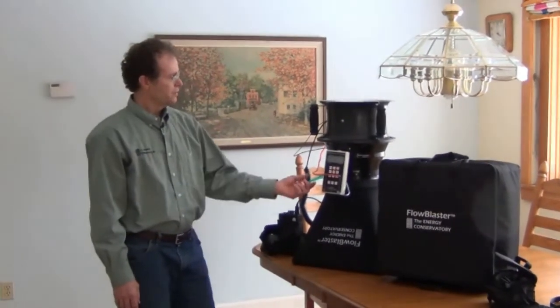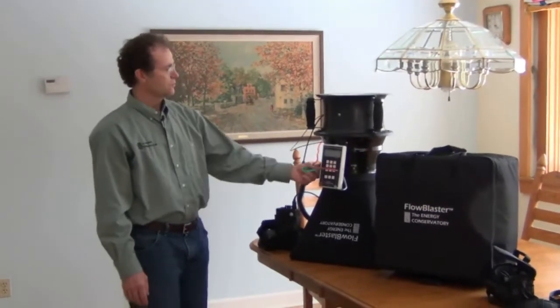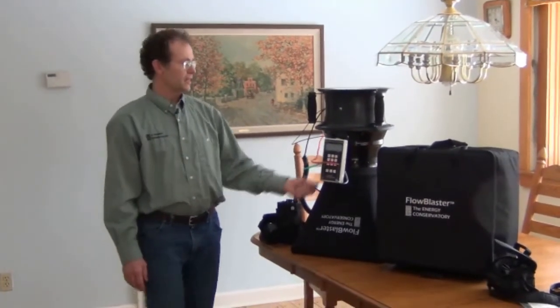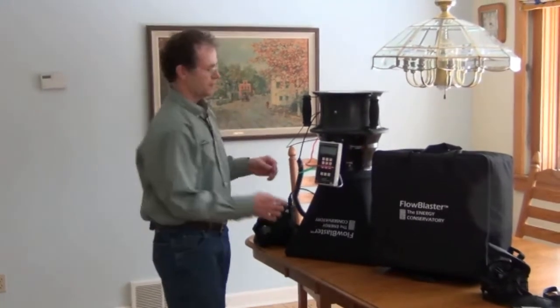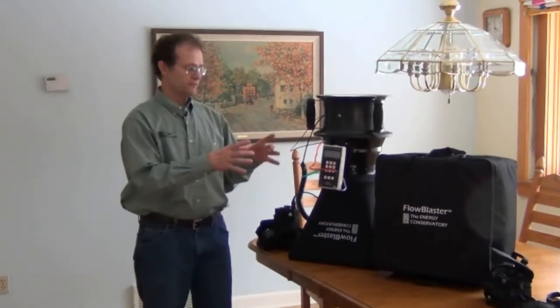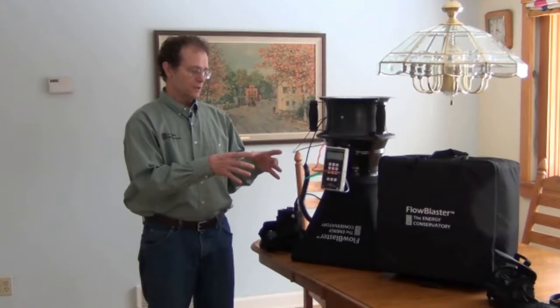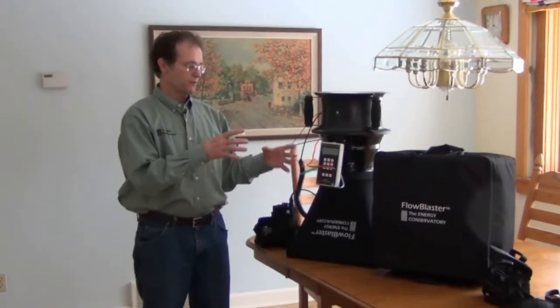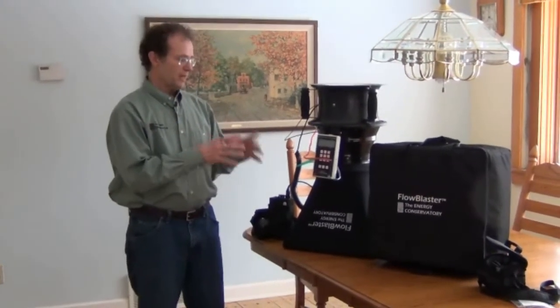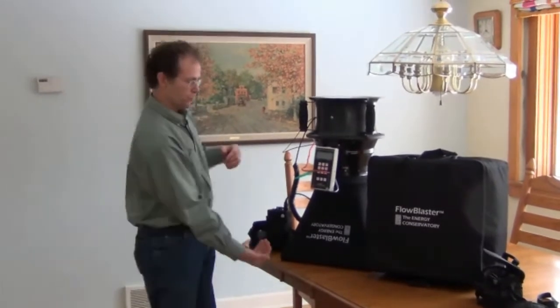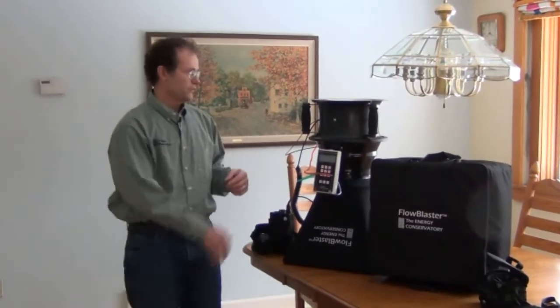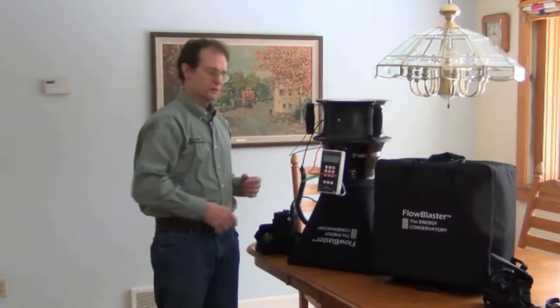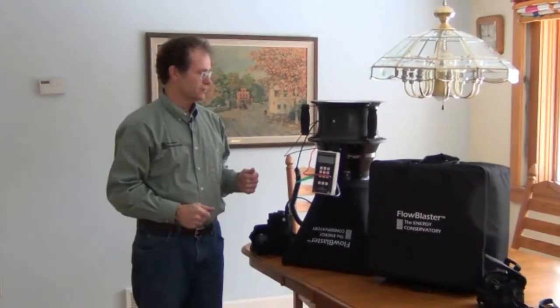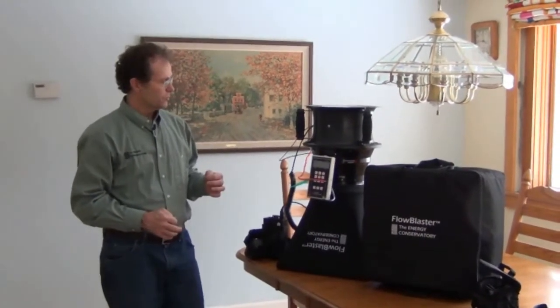The hose setup, input on channel A will go to the supply tap. There's a supply and a return tap. There's flow sensors inside the device with 2 flow sensors, one's for supply, one for return. The supply has the sensors pointing down towards the flow. The return, the flow will be the opposite direction. So the second flow sensor for return has holes pointed in the other direction.